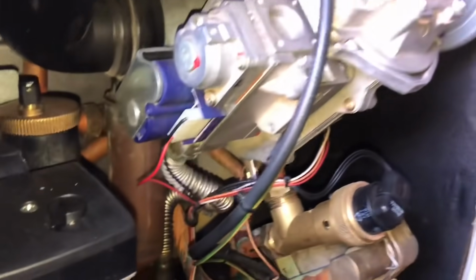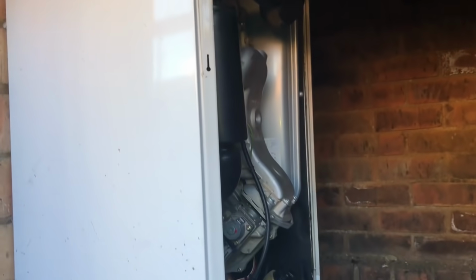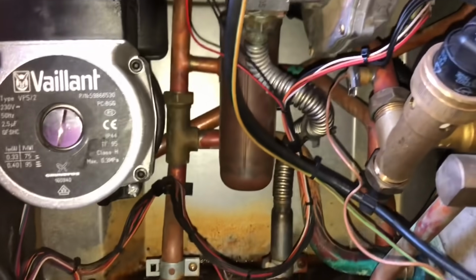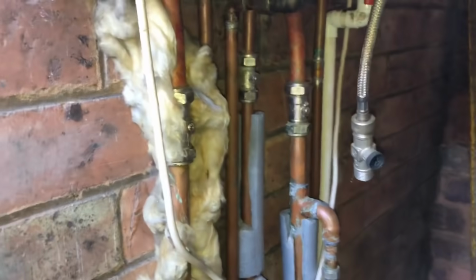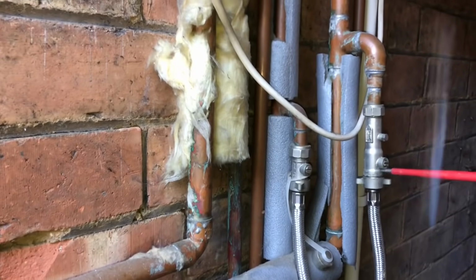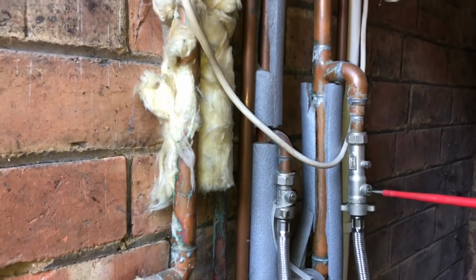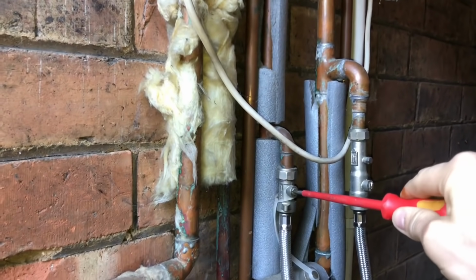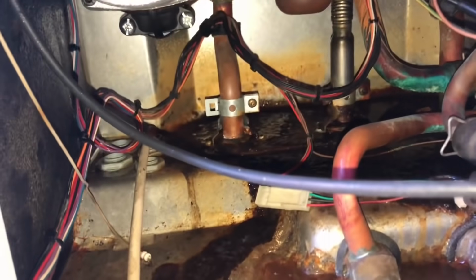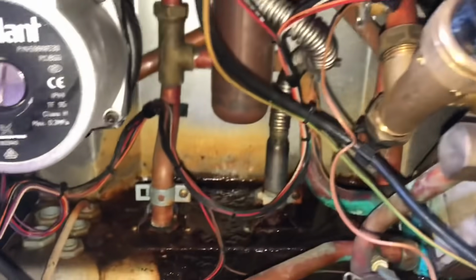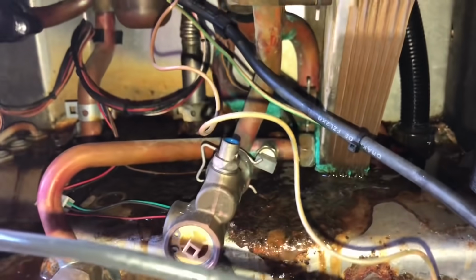So, the reason I'm filming this, what I would do now, start at the top, because although the water's down there, it could be something dripping at the top that's coming down and then eventually ending up there. So I always start at the top, see what I can see. If it's dry, then move down until you find something that's weeping. And also what I'm going to do is, because I have had a look so far and I can't really tell where it's coming from, because the pressure is on 0, it's already leaking, it's outside, it don't really matter if it leaks anymore, so it's filling leaks, knackered. Going to put some more water in the system, so hopefully we can tell where it's coming from. I would say shout up if you can see it, but you're not here. It's getting worse.